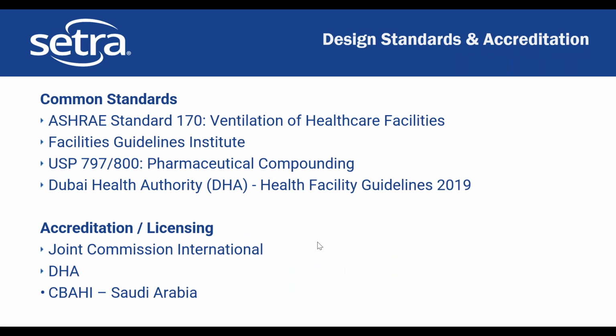So let's talk about the primary standards that are involved in the healthcare space. The very top standard that is most common is ASHRAE 170, ventilation of healthcare facilities. This standard covers everything from air changes per hour, pressurization requirements, temperature, humidity for all healthcare spaces. ASHRAE, in hand with the Facilities Guidelines Institute, covers a majority of what you see in the United States and across the globe, and in MEA and India.